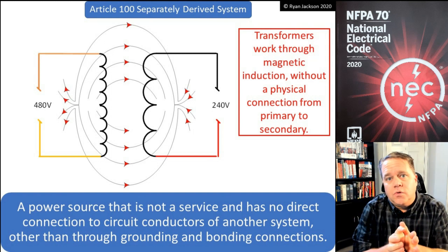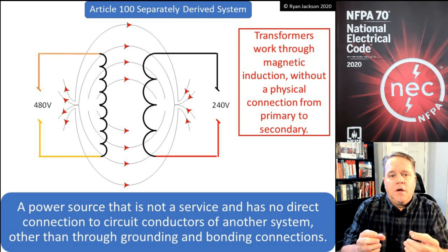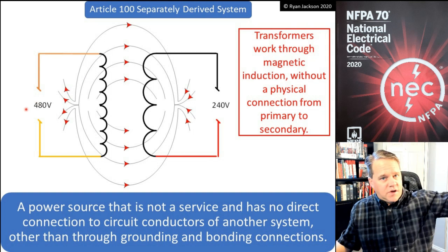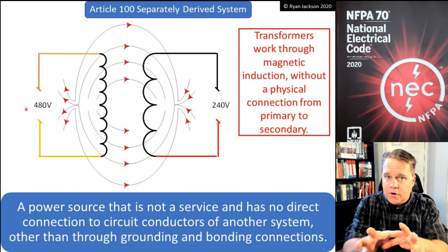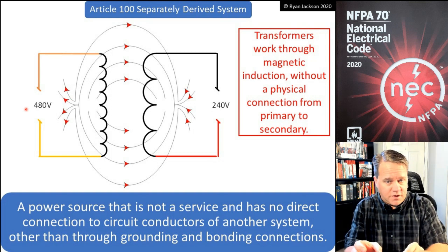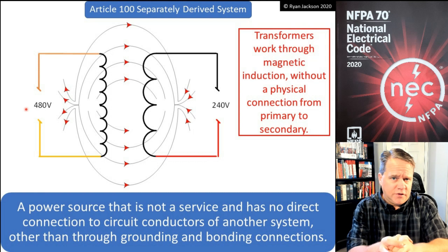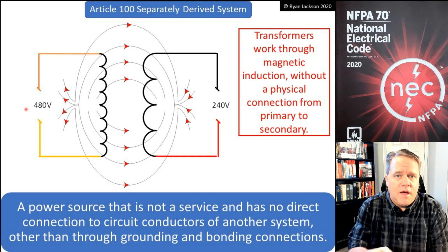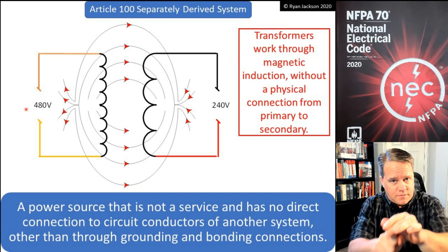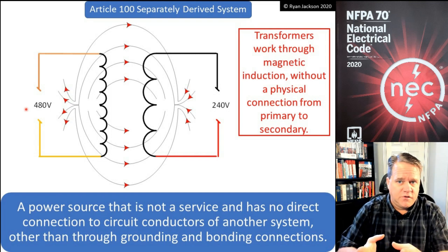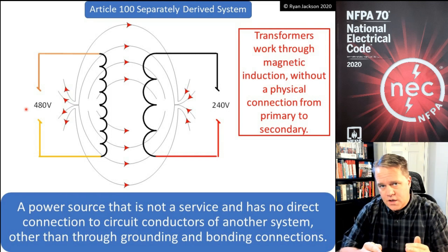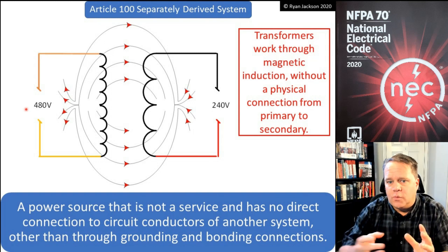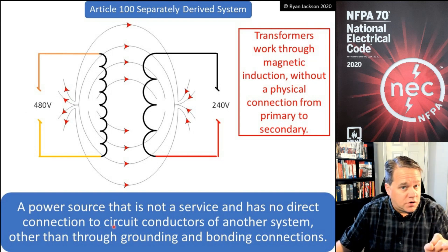On the utility side — say 480 volts — we bring it into the primary of the transformer. There's a green wire that connects to the metal parts of the transformer. We then generate a new system, maybe 240V or 120/208V, and that system also has a green wire going to its metal parts and back to the first system's disconnect. So ultimately the two are connected through green wires, but that's only through grounding and bonding connections — not a direct circuit conductor connection.